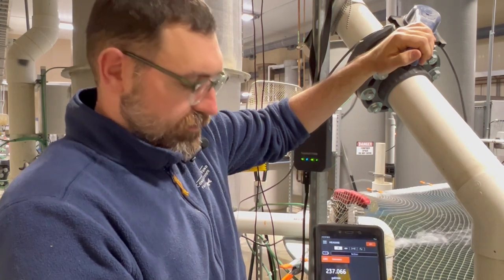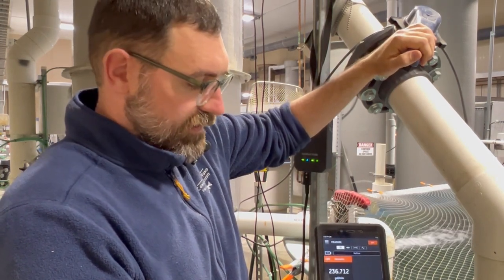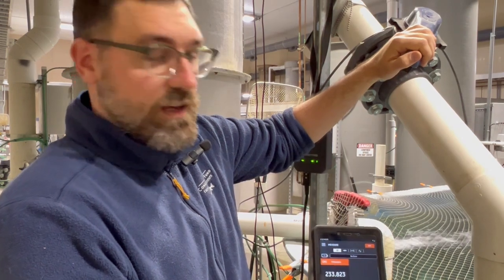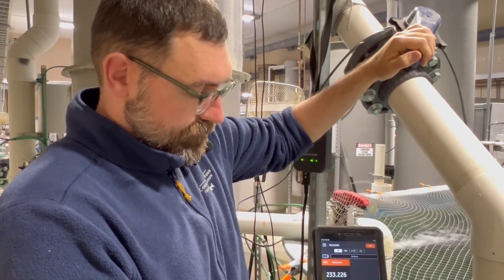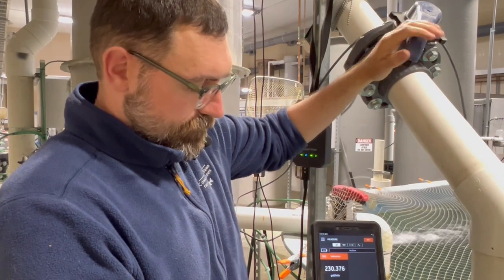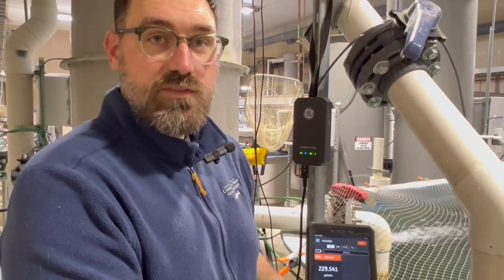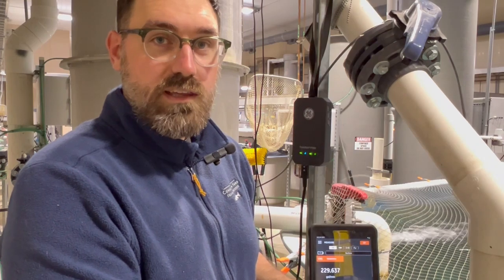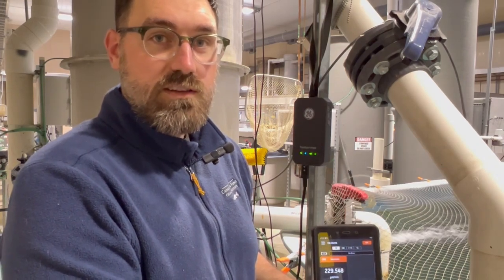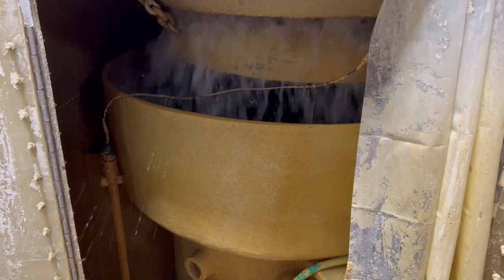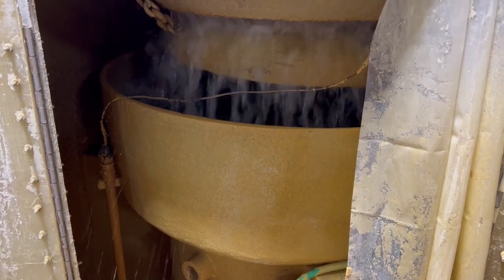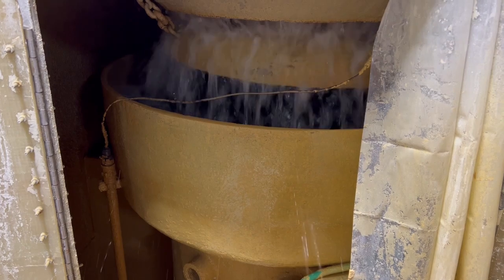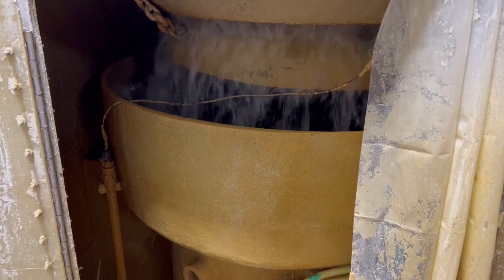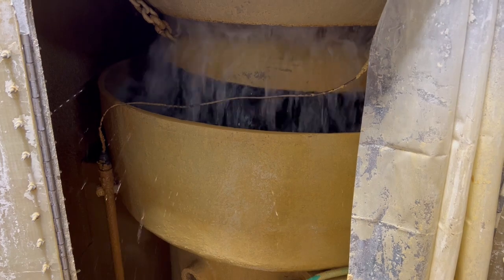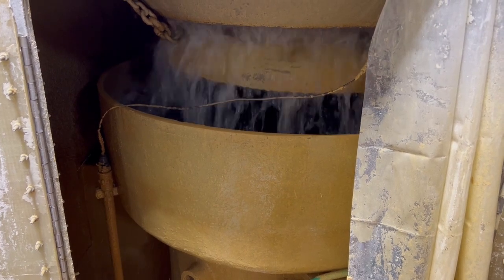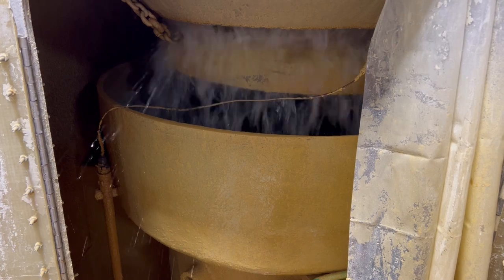So just a little adjustment on the butterfly valve and we're seeing the flow rate react in real time. We'll let this sit like this for about a minute or two just to come to equilibrium, and then we'll walk around and check the LHO and see how it works. Now that the flow rate for this system has been returned back to the engineered spec flow rate, you can see that the LHO is not overflowing and we are getting maximum oxygen transfer efficiency.